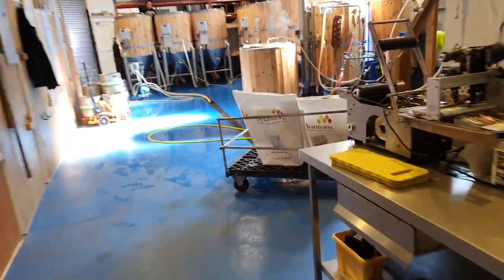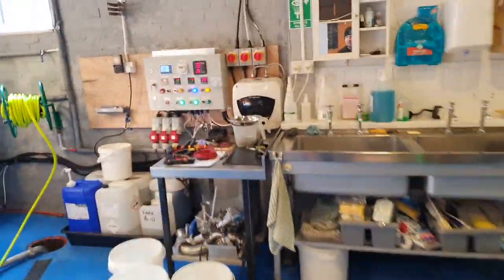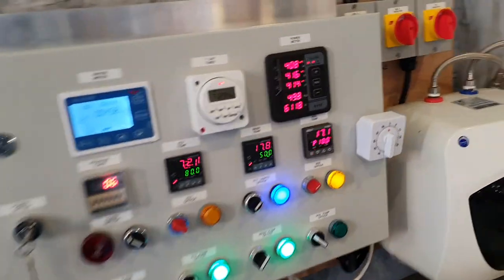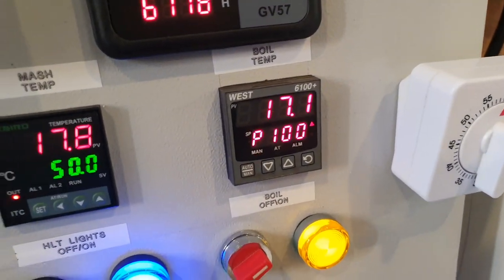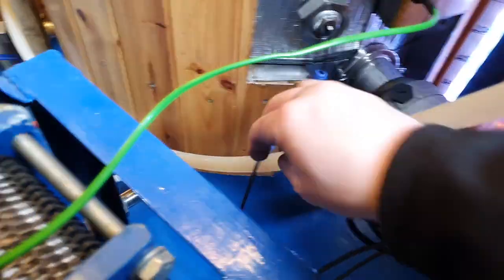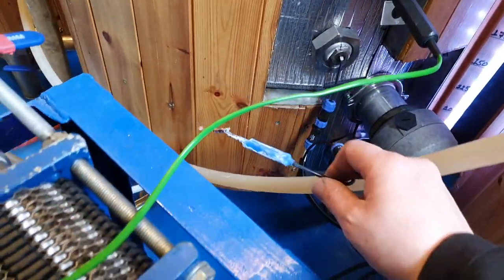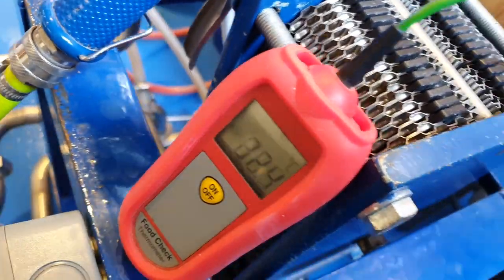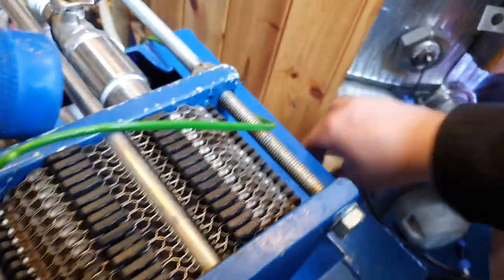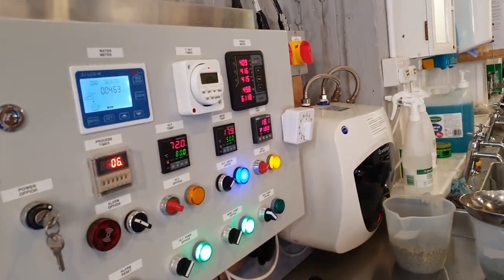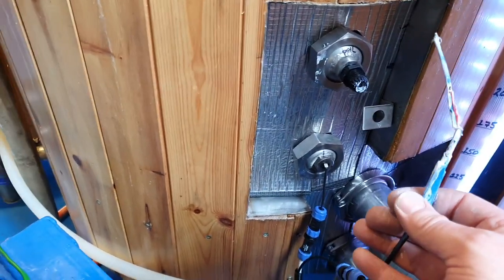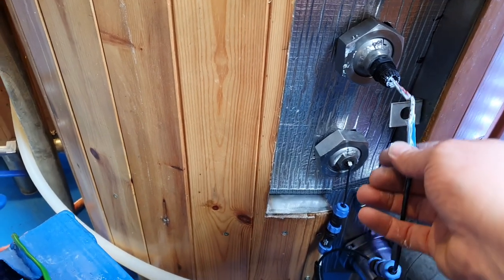Pleased to say that problem's cured, but we have another one. Unfortunately, the thermo probe for the boil, which is coupled to this West 6100 Plus, is playing silly buggers. So I've got him hanging out here. I've tried several things, earthing the shielding - we are at 88 degrees. So I'm measuring it manually at the moment, but if we look at the probe temp, you see it says 18.2 on there. This is just bare metal, and it's not earthed at the other end.